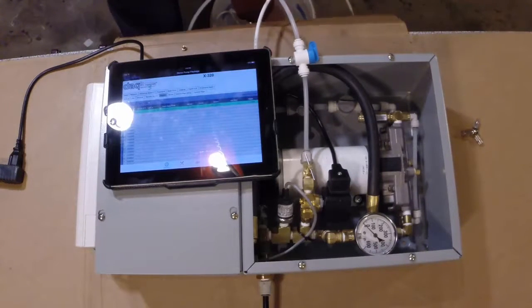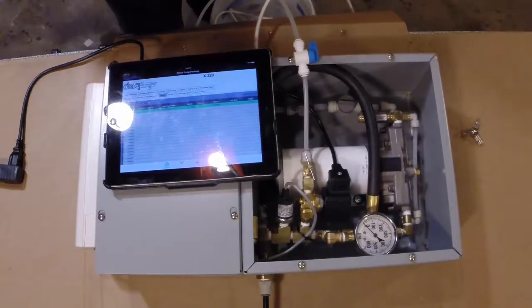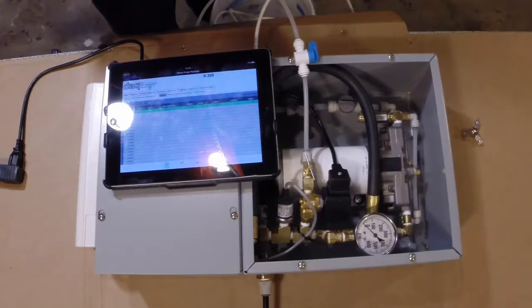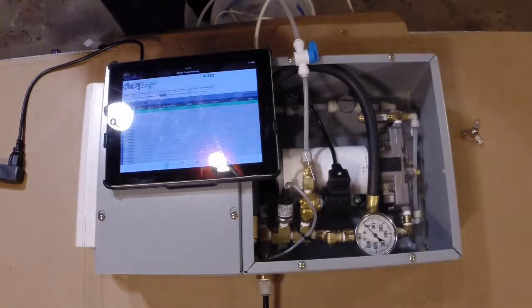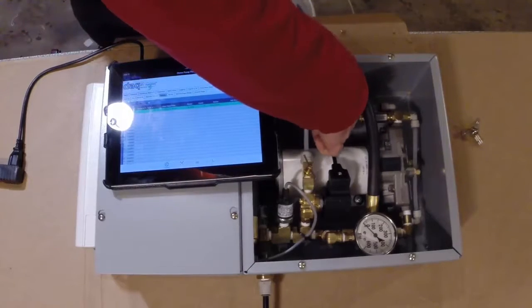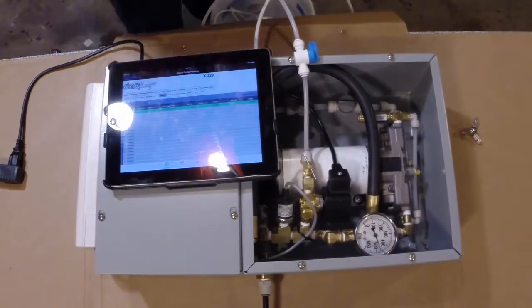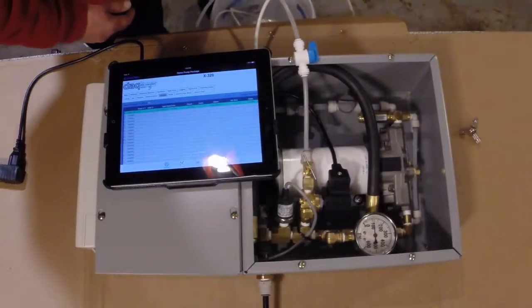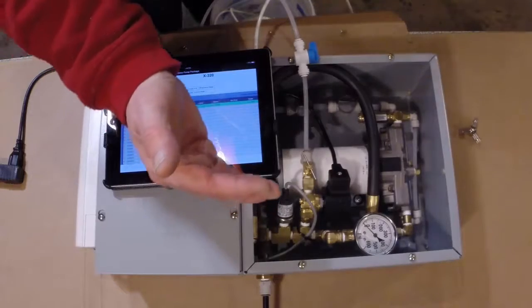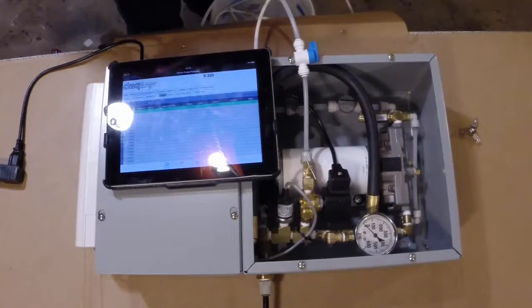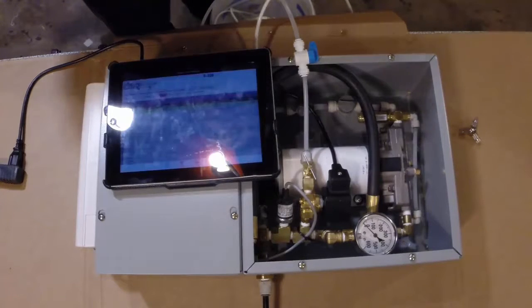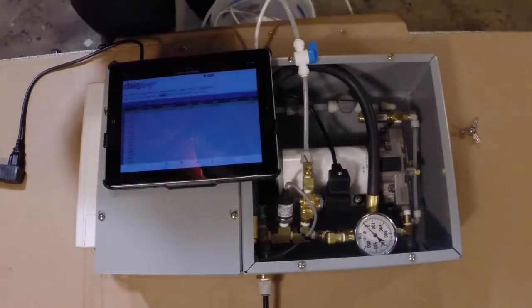But it is set up, this pump is actually set up to feed it through a gravity feed. Right now, we don't have a gravity system. We actually have city water coming into it. But this line here where this valve is, that's actually supposed to go down into the supply line. So when it does shut off, the high pressure liquid that's still in the line will kind of quickly back feed into the reservoir where you won't lose any fluid in the gravity feed system.